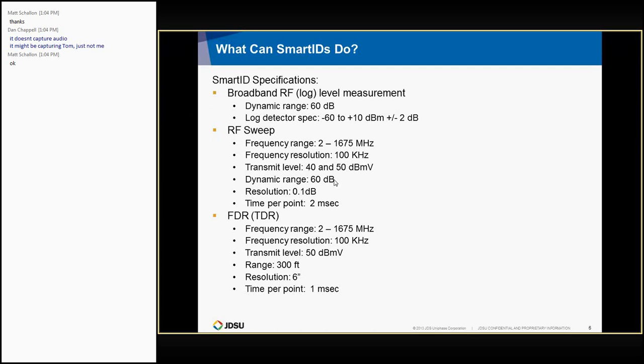One other thing I want to point out is that when you're doing end-to-end sweeps, which is the RF sweep, it takes about 2 milliseconds per frequency to move through a range of sweeps. So if you're doing like a 300-point sweep, you're talking about 0.6 of a second per sweep. And the FDRs normally involve 1,000 points or 1024 points, so they take about a second per sweep. And this thing does a lot of sweeps when you're doing the test, so the time adds up a little bit.